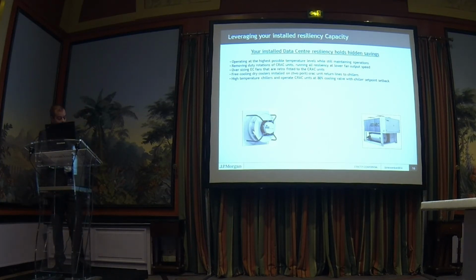Because at the end of the day, in every chiller, in the bottom down there in the shell and tube, the refrigerant is always held at 0 or 1 degree refrigerant temperature. So if you're running at 10 degrees, you've got 10 degrees difference between the refrigerant temperature and the water output temperature. If you're running at a 20 degree output temperature, you've now got 20 degrees of difference between the refrigerant temperature and the output target temperature set point. So in essence, the heat exchange in the shell and tube evaporator just goes through the roof. Then the chiller actually has to work less, with less refrigerant movement and less compressor power, because it's running at a greater delta.